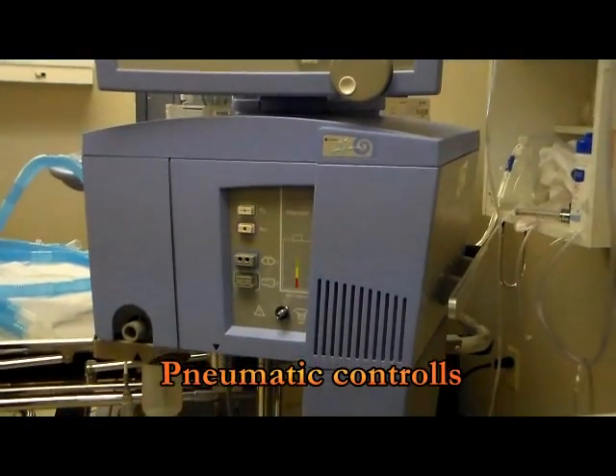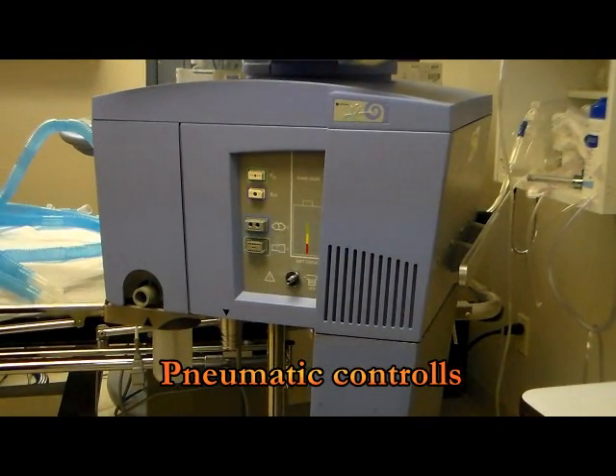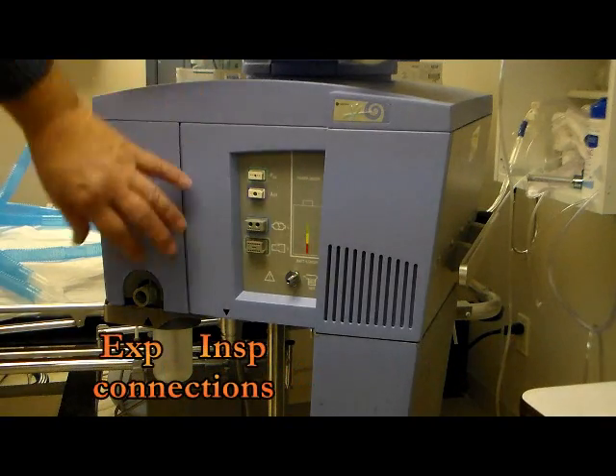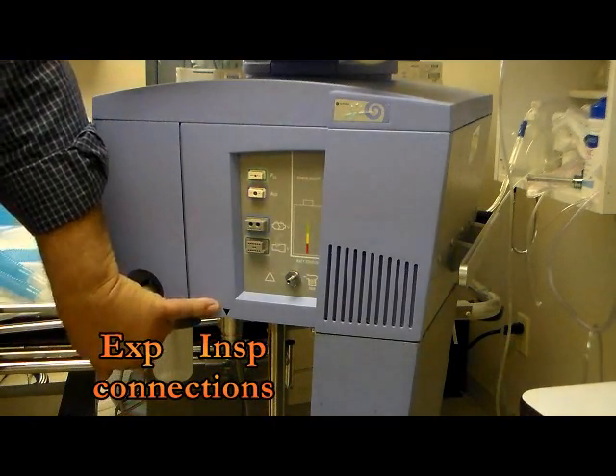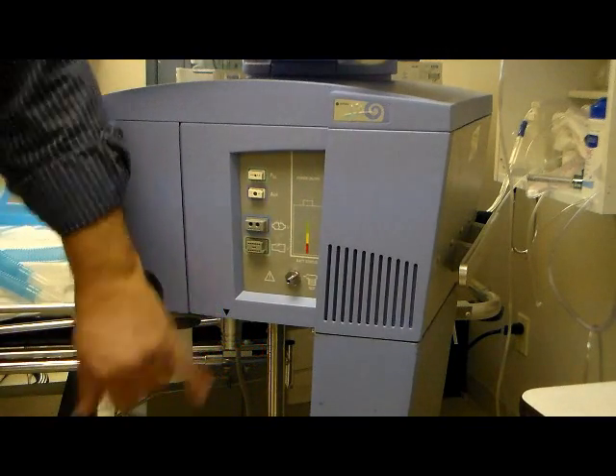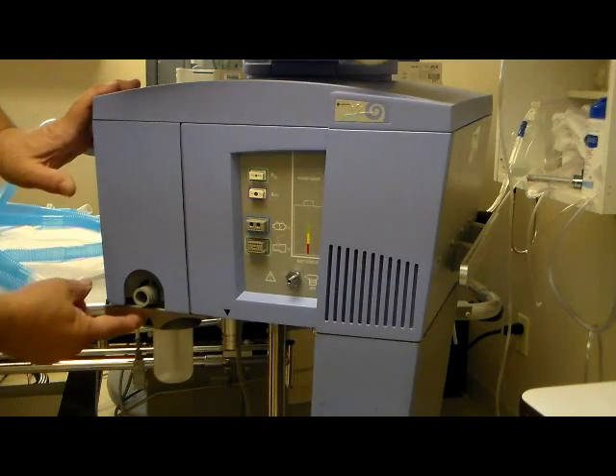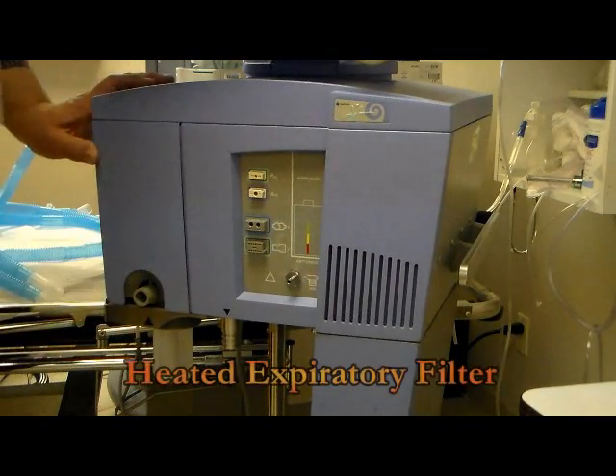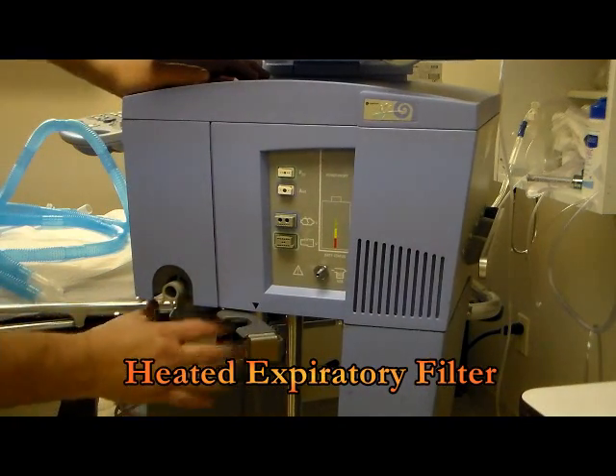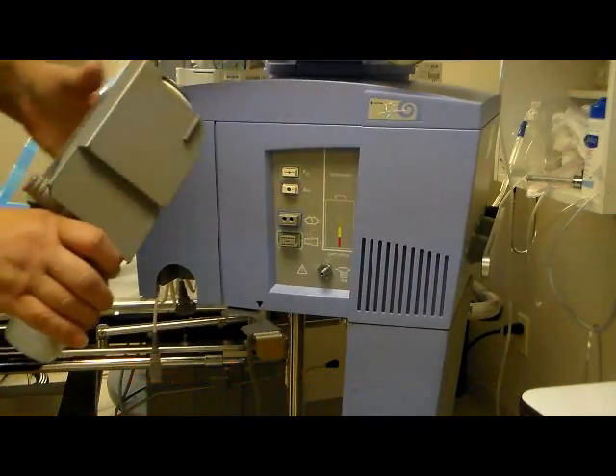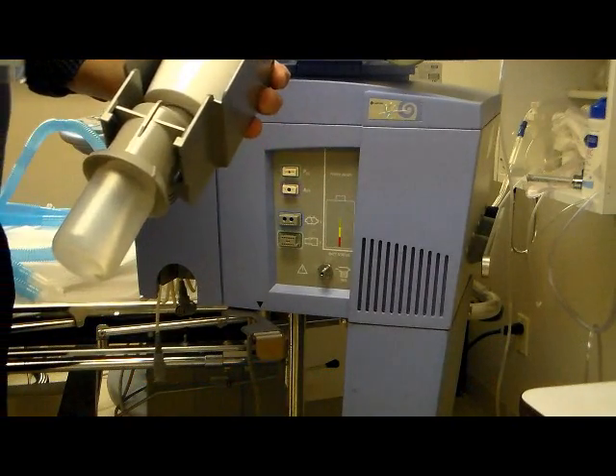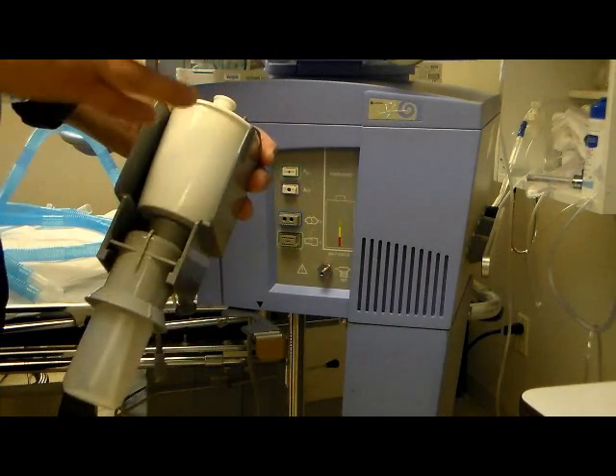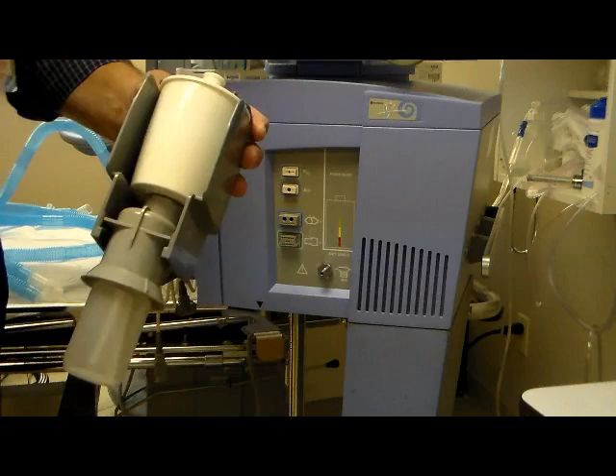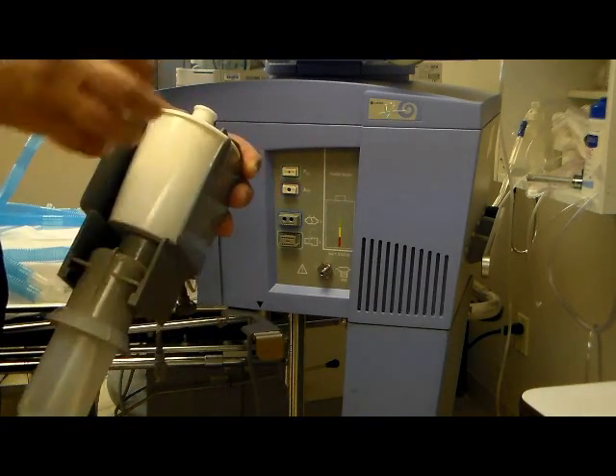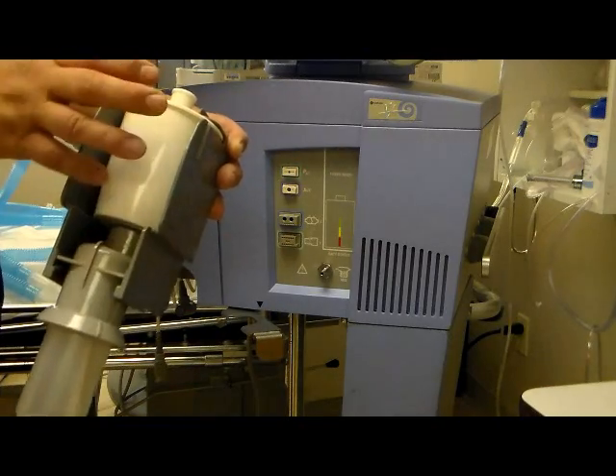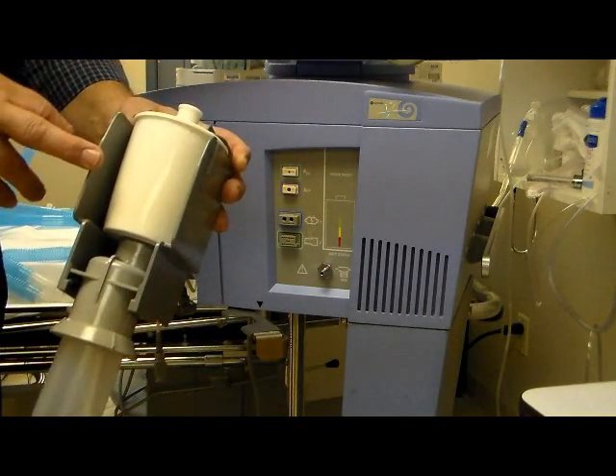Okay, the pneumatic section of the ventilator is just below the screen, and we have the inspiratory arrow going to the patient and the expiratory arrow coming into the ventilator. One thing I do want to point out is with the Avea, you have a heated HEPA filter. This HEPA filter maintains the vapor phase of the moisture, so it tends to not get clogged up as easily as some of the other ones. This is recleanable, or you can get disposable units.